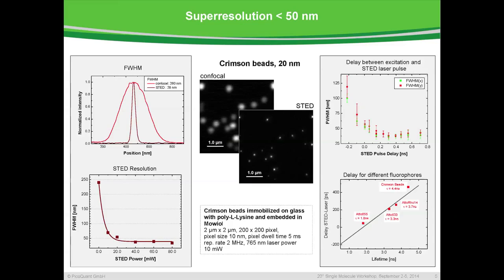In addition, there are other parameters that you can choose. To the right, you see the delay between the excitation and the STED laser pulse. We plotted the full-width half maximum in X and in Y for fluorescent beads over the pulse delay between the two pulses. If you go to the optimum, you have well below 50 nanometer resolution, and this is a quite robust parameter — you can add plus or minus 200 picoseconds between the two laser pulses and still be below 50 nanometers. Interestingly, this delay is different for different fluorophores; it actually depends on the fluorescence lifetime. For one nanosecond longer lifetime, you have to add approximately 150 picoseconds between the two pulses.